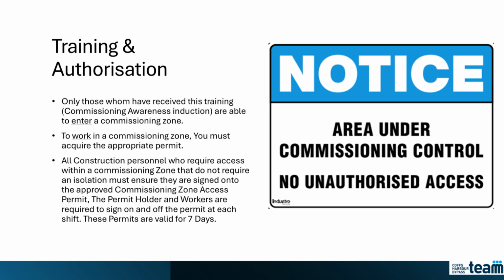Only people who have completed this commissioning awareness induction are allowed to enter a commissioning zone. To work in a commissioning zone, you must also hold the appropriate permit. Construction personnel who need access inside a commissioning zone but do not require an isolation must be signed onto the approved commissioning zone access permit. The permit holder and all workers must sign on and off the permit at the start and end of each shift. These permits are valid for 7 days. After that, a new permit is required. If you are unsure whether you have the right permit, stop and check before entering or starting work.